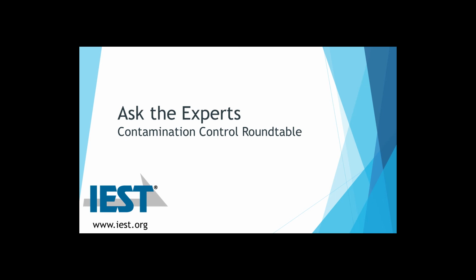Okay, very good. So we're back to the classification and qualification of the room itself. The isolator, because of how it's designed and the fact that it goes up into the ceiling, actually occupies its own footprint with its own air. So when you look at the 8 background or the 7 background, depending upon what you have, generally you do deduct that piece of equipment because it is its own self-contained unit. And then the number of samples to meet Table A1 is a calculation based upon the remaining area. Did that answer your question?